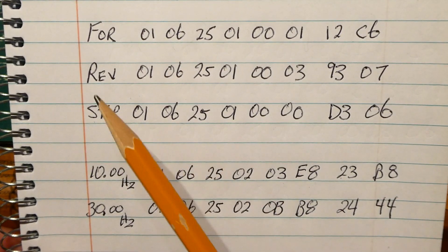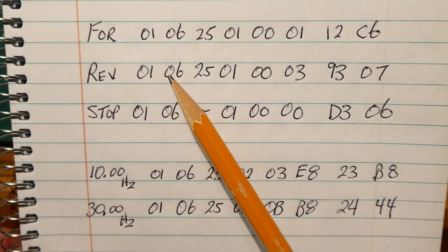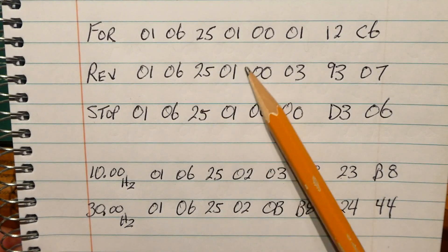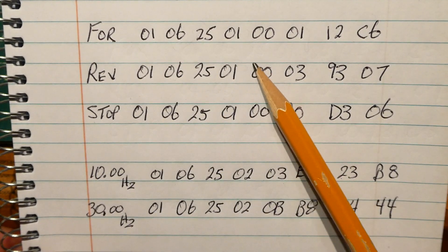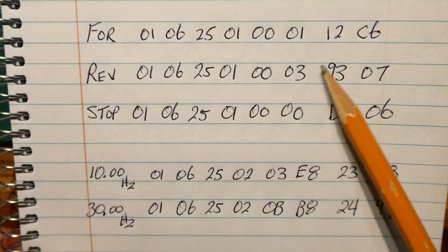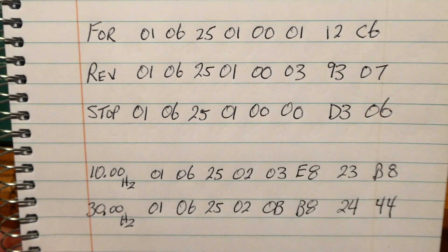So for reverse, same thing, 01 is address, 06 we're doing a write to this address here, this register, 2501, and we're writing 0003 as the data, and that will give us a reverse, and we have a 16-bit CRC.